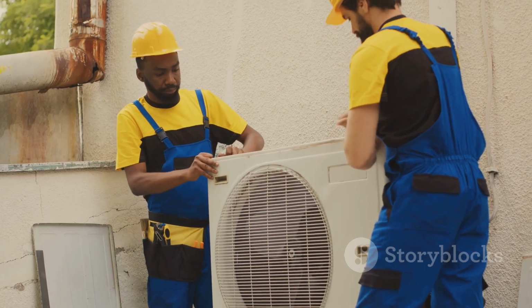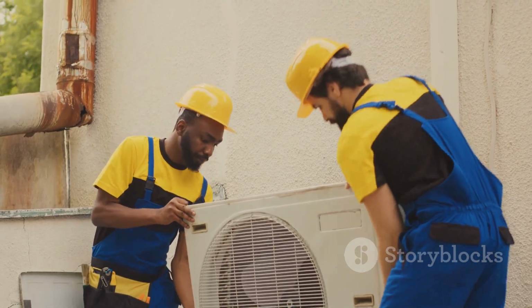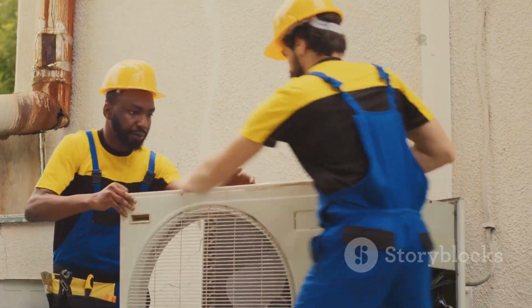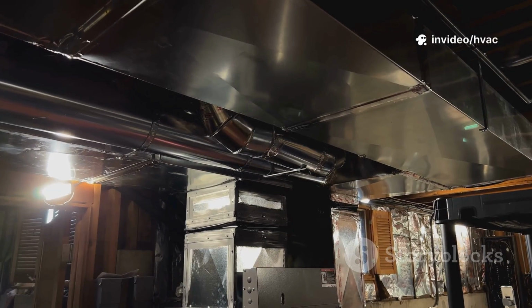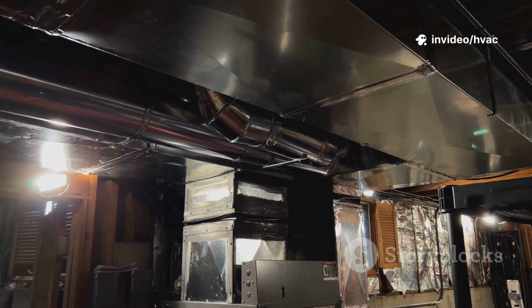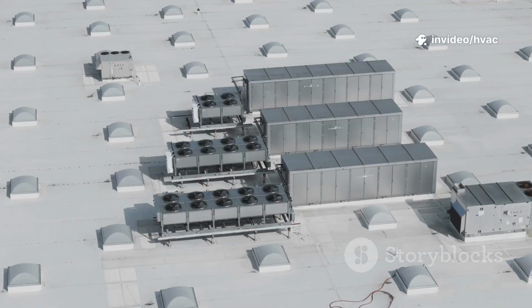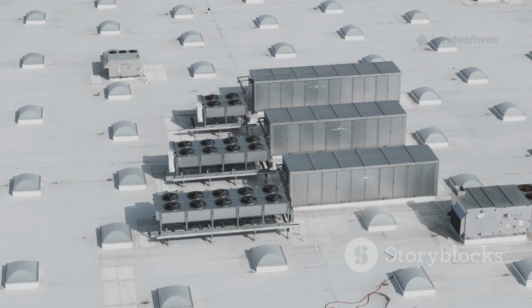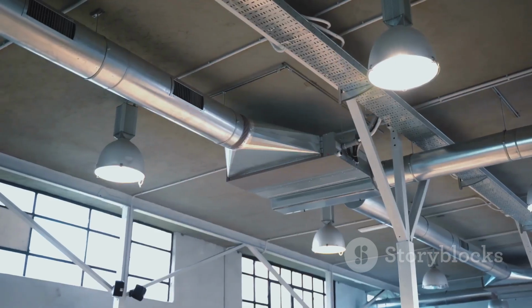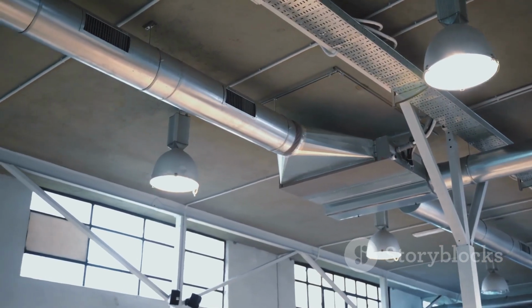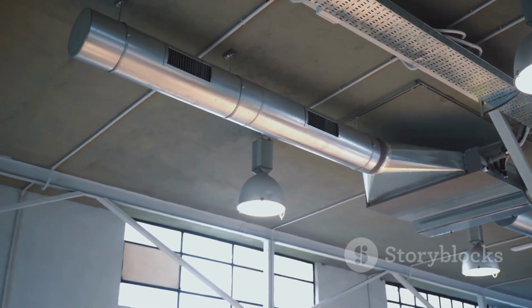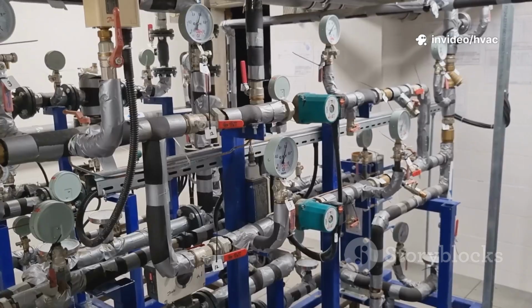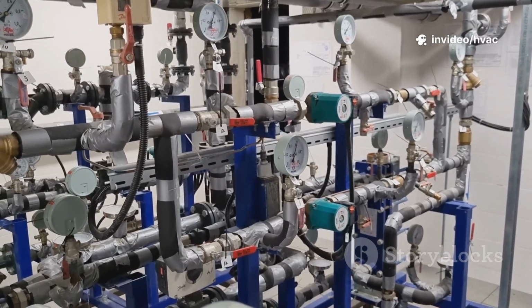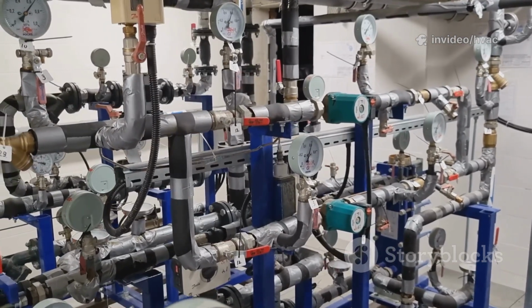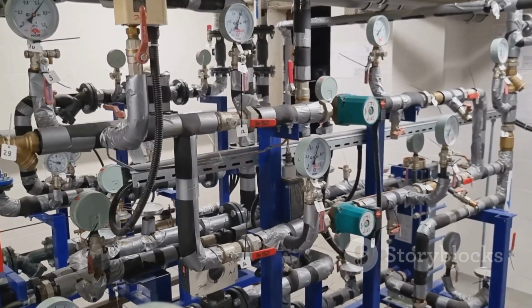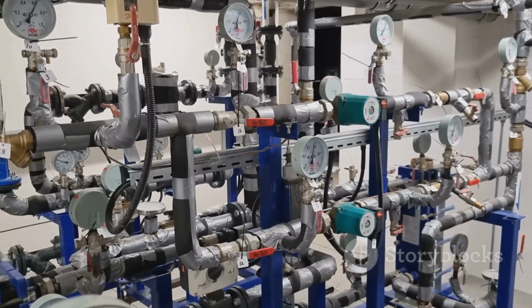They are commonly used on terminal units that provide heating or cooling to individual rooms or zones. These units include fan coil units, which are often found in hotel rooms and offices, and air handling units, which serve larger spaces like lobbies or entire floors. Chilled beams, another type of terminal unit, also benefit greatly from the precise flow control offered by a PICV. By using a PICV on each of these units, the entire hydronic system becomes easier to manage and more efficient, as each part of the system gets exactly the water it needs to operate correctly.